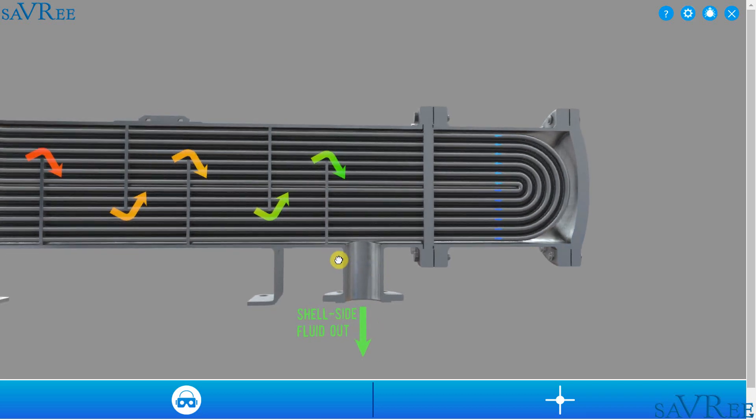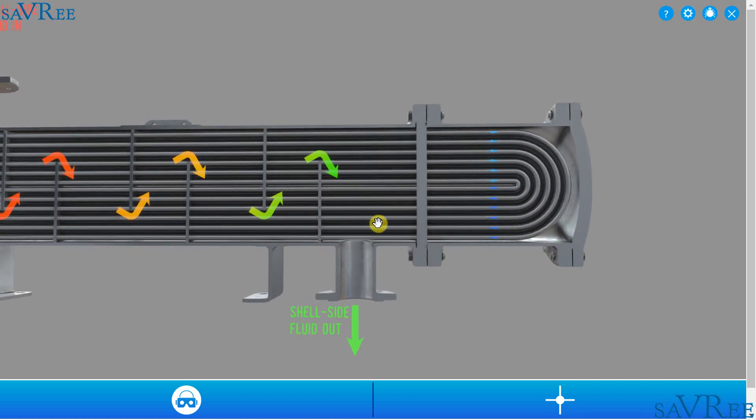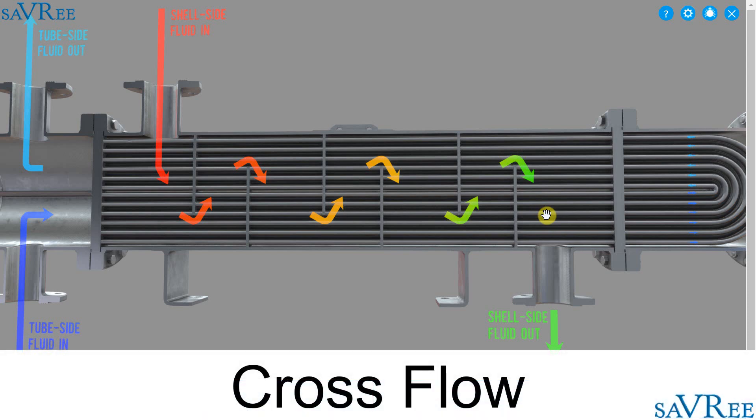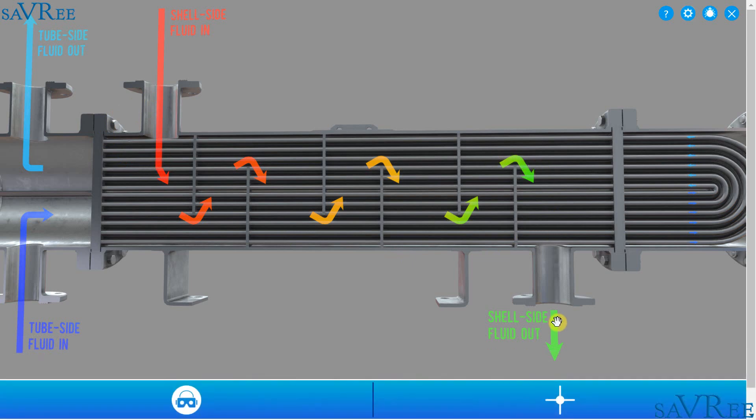I have to say it would be slightly better if this discharge port from the heat exchanger was more to the right in order that it could flow through the heat exchanger and down on the right hand side rather than here. But that is how the heat exchanger has been built in 3D here. The reason for this criss-crossing pattern, this is actually called cross flow, is because we want to maximize the heat transfer between the two flowing fluids and we do this by having a cross flow pattern. There's no point the fluid entering in the top flowing directly here and then dropping out of the bottom. Because if we do it like that, we've had very little turbulent flow and there's not going to be as much heat transfer between the two mediums compared to when we do this cross flow pattern.